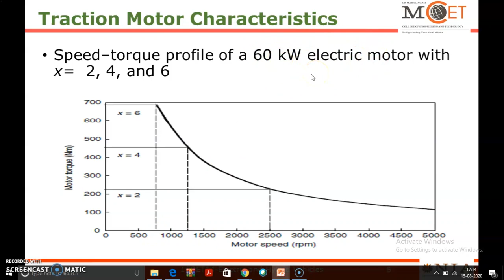Next, we have seen the variable speed electric motor characteristics. Whenever the motor speed is less than the base speed, it is said to be the low speed region. Whenever the motor speed is greater than the base speed, it is said to be the high speed region. In the low speed region, the torque remains constant but the motor power is linearly increasing, whereas in the high speed region, the motor power remains constant and the torque is decreasing.